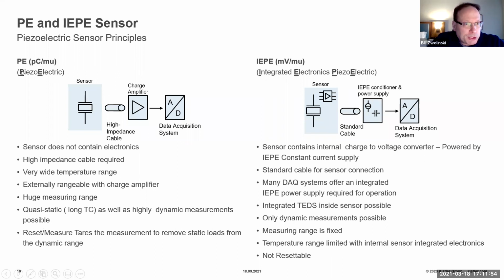And basically this measuring chain, piezoelectric, is completely rangeable. Unlike a strain gauge, where you're often sizing the strain gauge based upon how much mass you have, how much dynamic or how much force you expect, and you live with the resolution. With a piezoelectric solution, you size the measuring chain for the dynamics of the event, quasi-static or dynamic measurement of the event, not necessarily the size of the load cell. It's not based upon the capability of a load cell. The performance is based upon how you range the measuring chain. So it's a completely different concept in terms of performance.